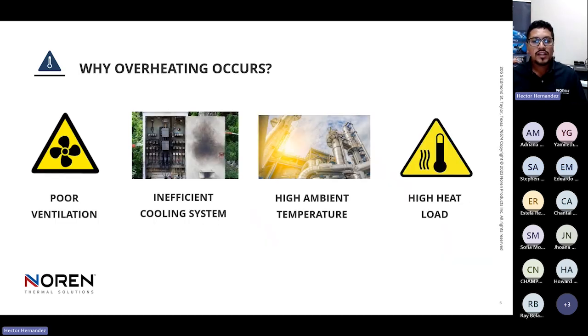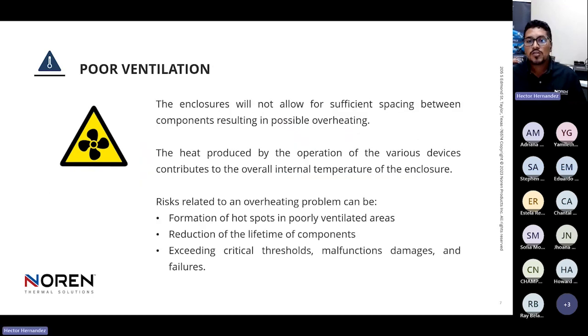But why do we have overheating? There are four main reasons. First, poor ventilation. The most used technology to cool down electrical panels is the two-fan technology: one fan introduces ambient air into the electrical panel, and the other fan exhausts this air. We must take care to correctly size the cooling needed for our electrical panel. For example, if we have an electrical panel with 1000 watts of heat and we install two 4-inch fans, probably these two fans are not capable of expelling all the heat.